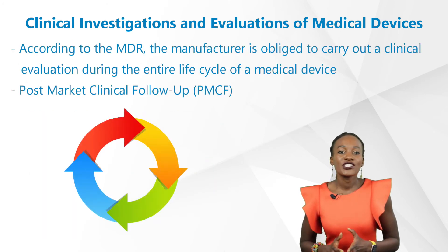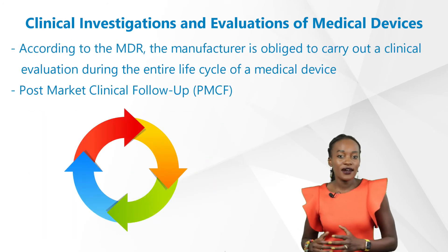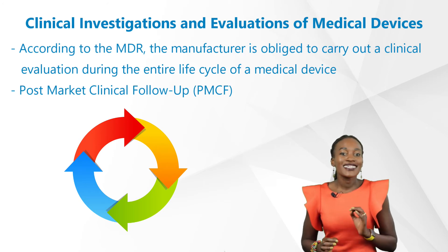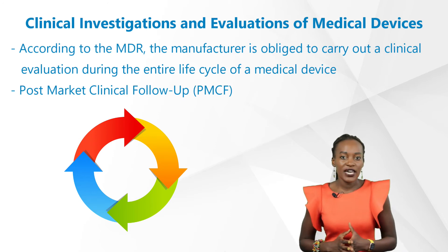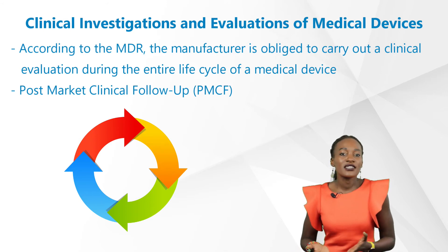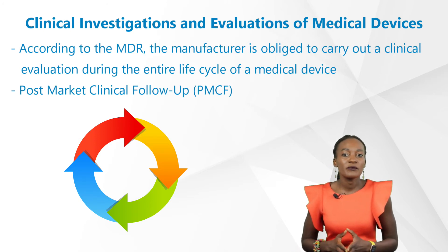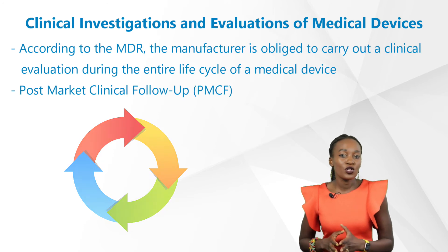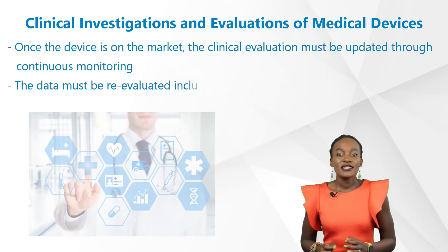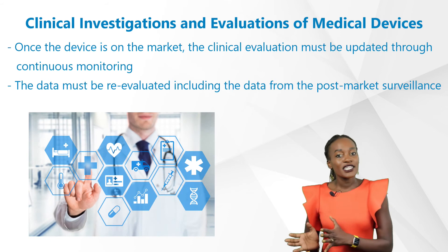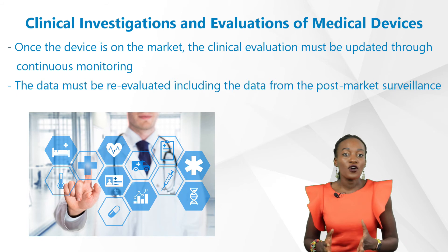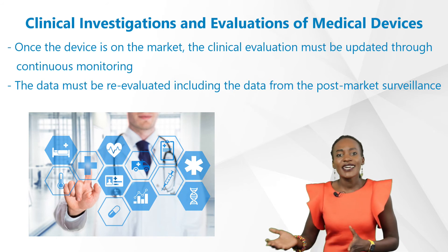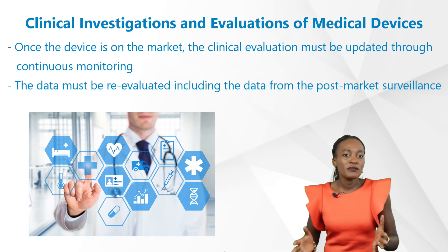According to the Medical Device Regulation (MDR), the manufacturer is obliged to carry out a clinical evaluation during the entire life cycle of a medical device — including after the device has been placed on the market. This includes conducting a clinical follow-up of the medical device in the market, also known as post-market clinical follow-up (PMCF). Once the device is on the market, the clinical evaluation must be updated through continuous monitoring of clinical performance and safety, especially regarding technical adaptations and optimizations of the device.